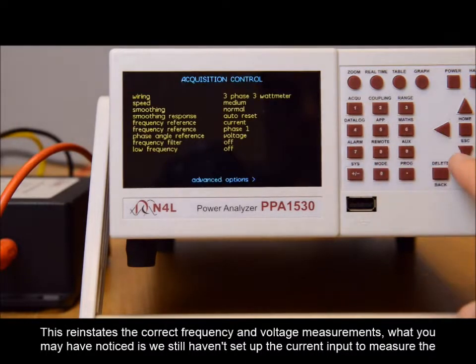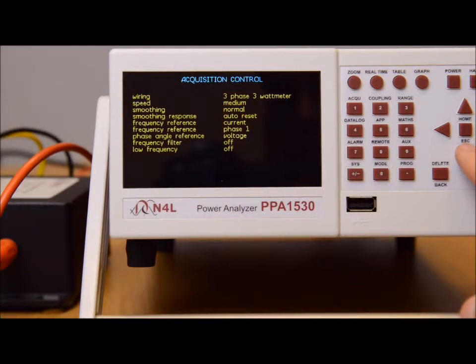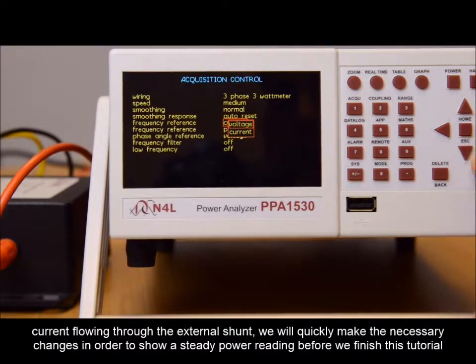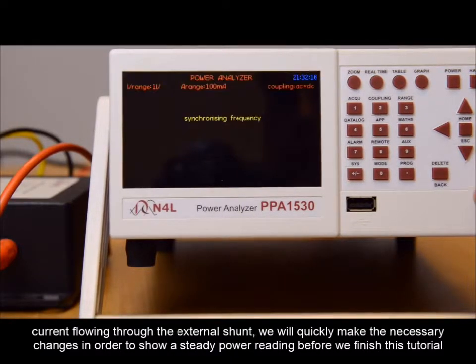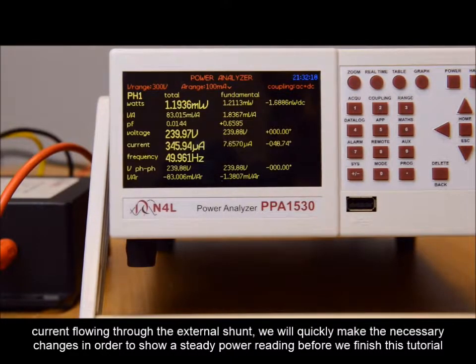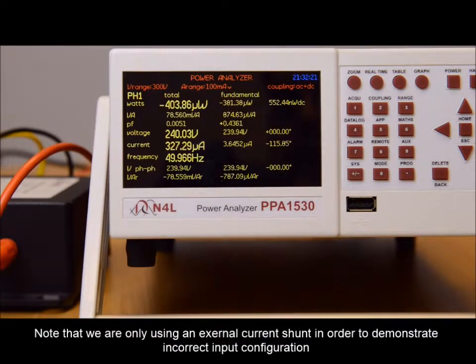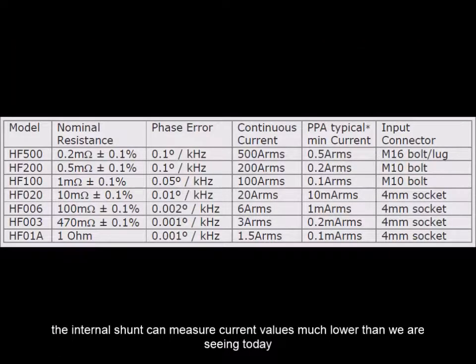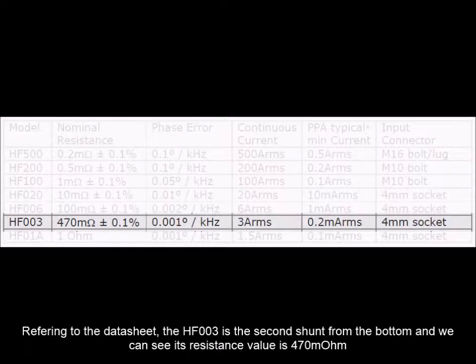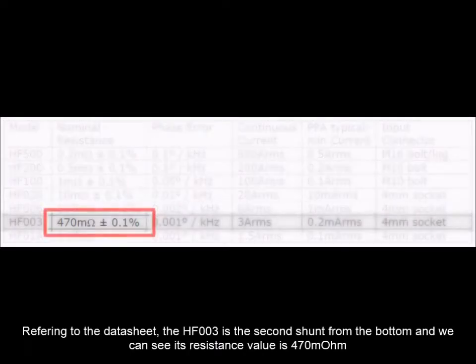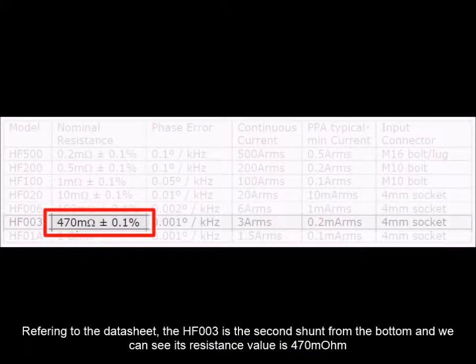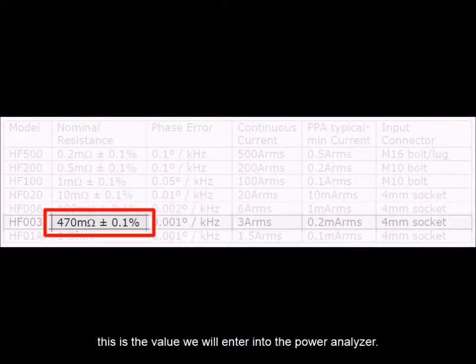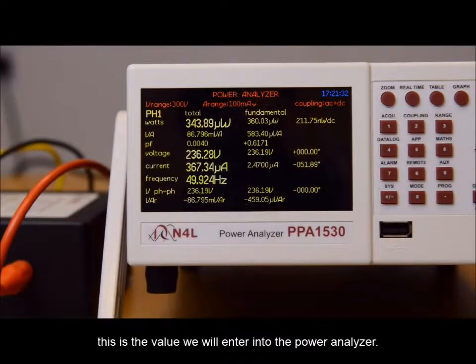What you may have noticed is we still haven't set up the current input to measure the current flowing through the external current shunt. We will quickly make the necessary changes in order to show a steady power reading before we finish this tutorial. Note that we are only using an external current shunt in order to demonstrate incorrect input configuration. The internal shunt can measure current values much lower than we are seeing today. Referring to the datasheet, the HF003 is the second shunt from the bottom, and we can see its resistance value is 470 milliohms. This is the value we will enter into the power analyzer.